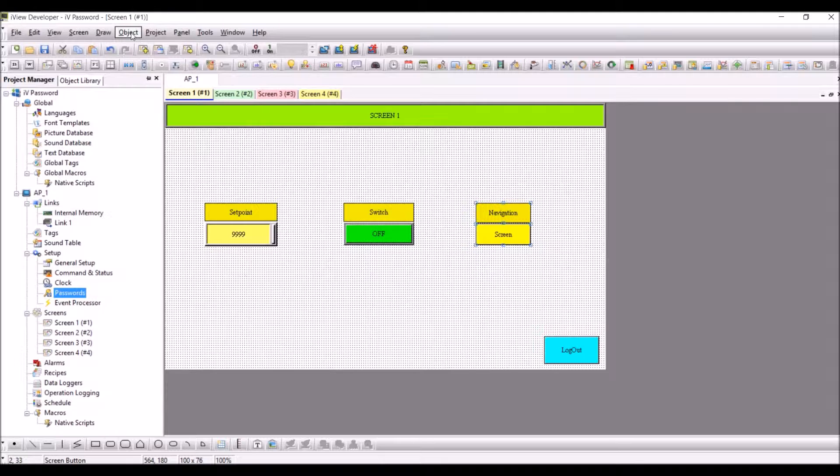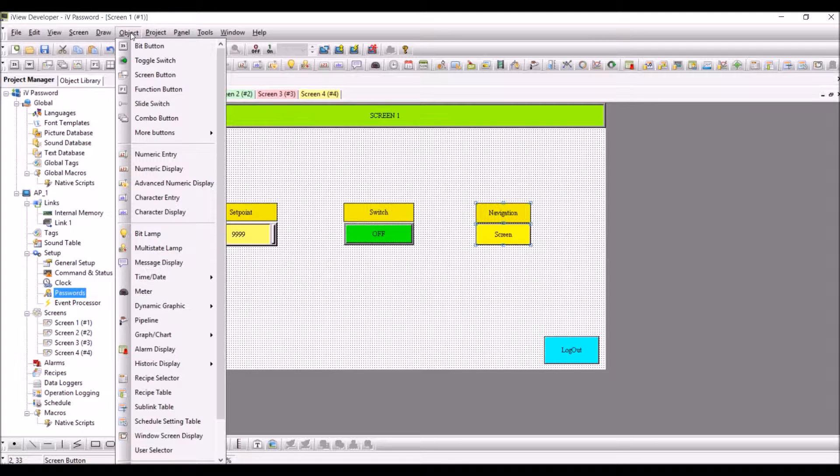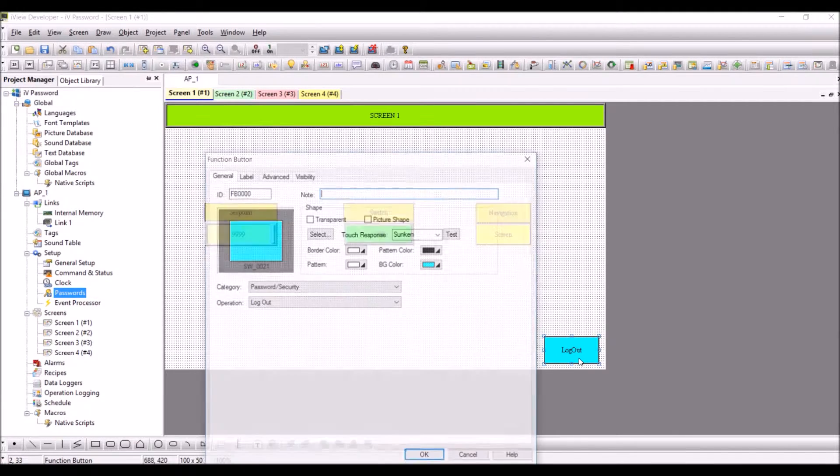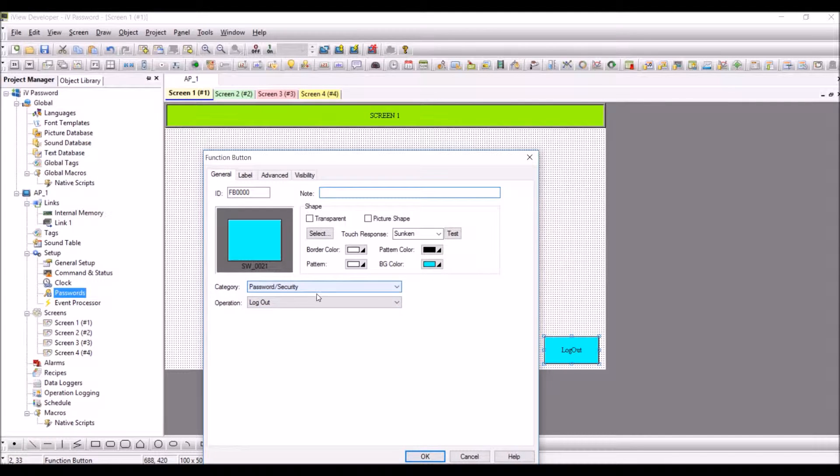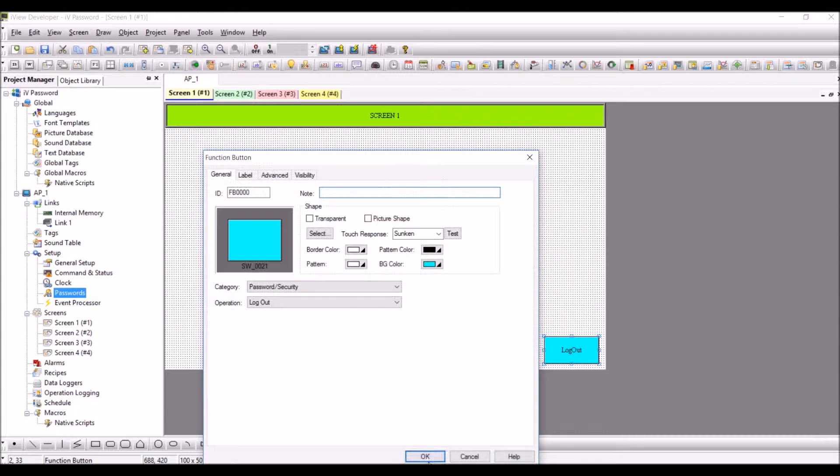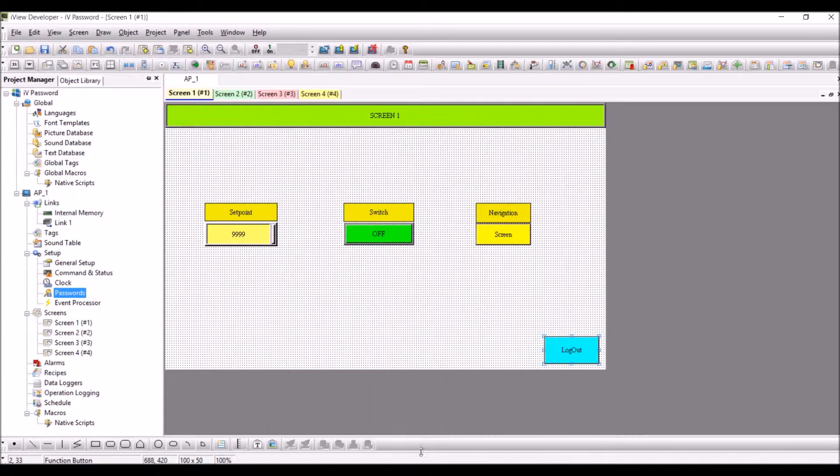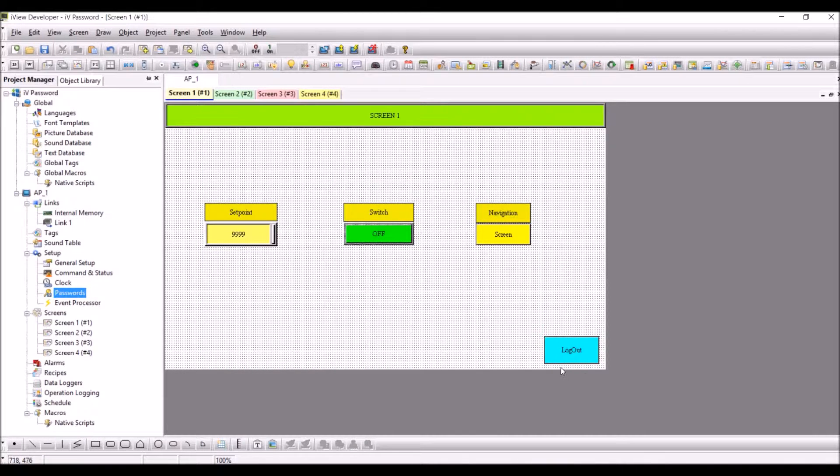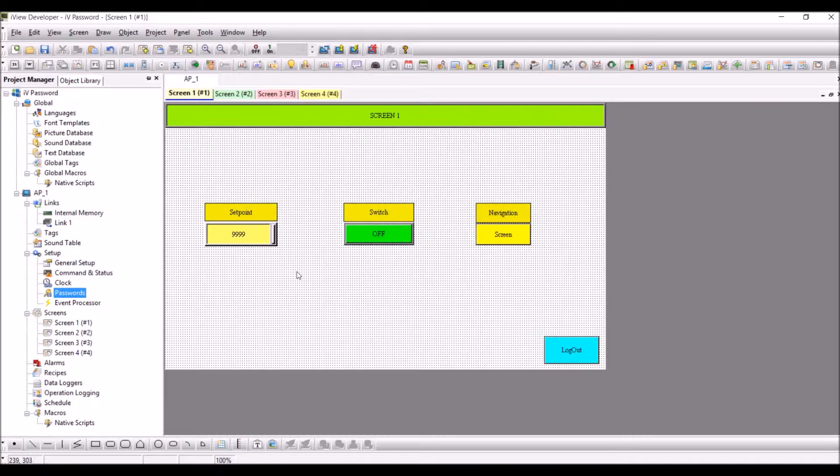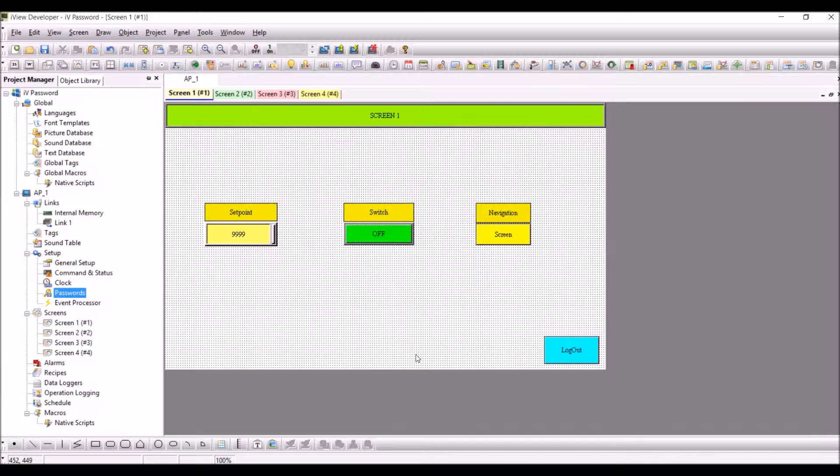Configure a function button object which you can get from object, function button. Select the category as password or security and operation as logout. Press OK. This button will act as a logout button from all the user levels which you have entered. Download the program and we will see how it is configured.